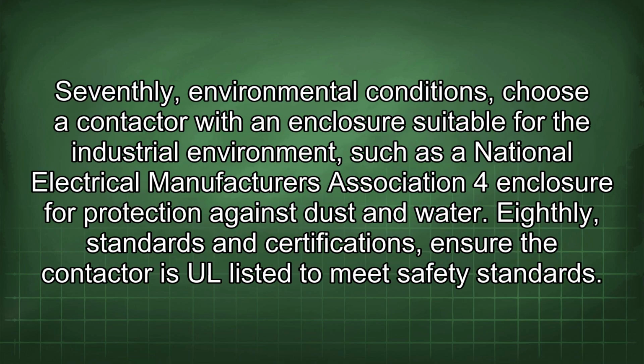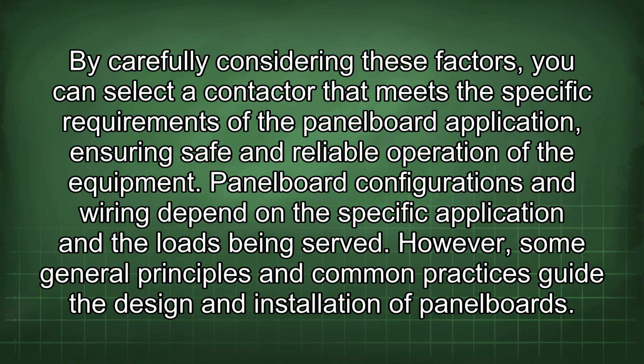Seventhly, environmental conditions. Choose a contactor with an enclosure suitable for the industrial environment, such as a National Electrical Manufacturers Association 4 enclosure for protection against dust and water. Eighthly, standards and certifications. Ensure the contactor is UL listed to meet safety standards. By carefully considering these factors, you can select a contactor that meets the specific requirements of the panelboard application, ensuring safe and reliable operation of the equipment.